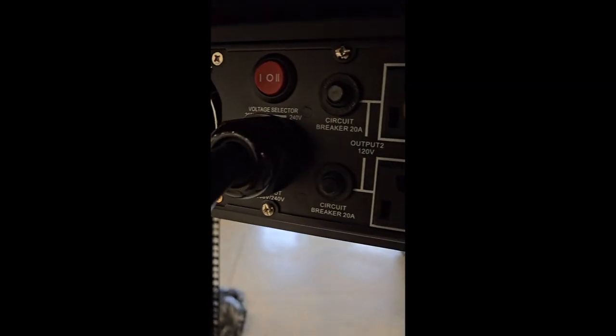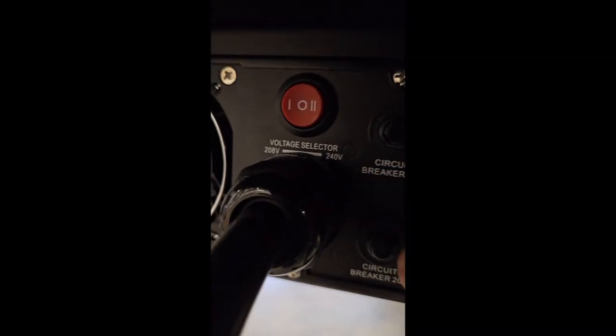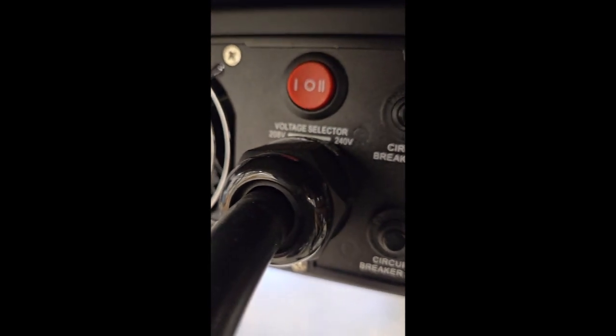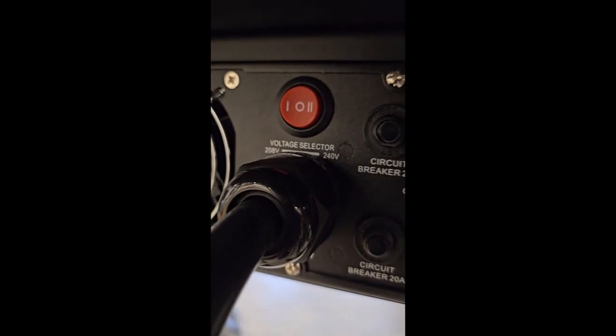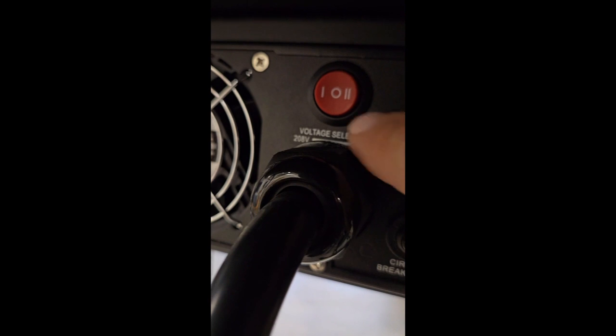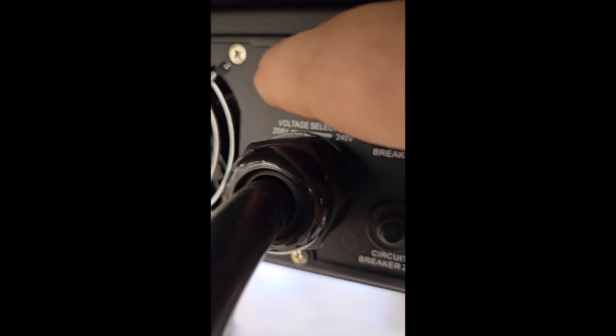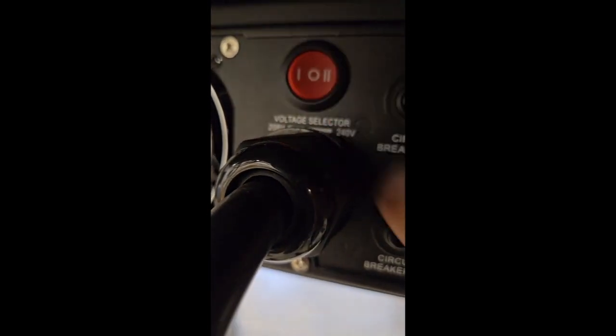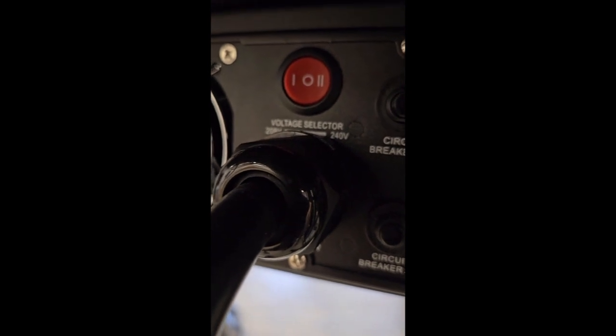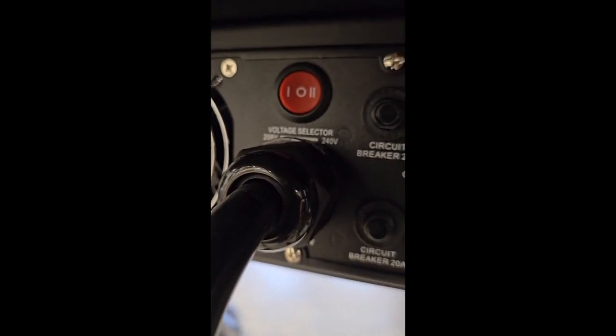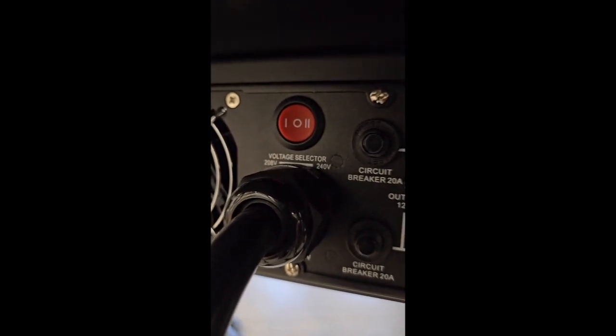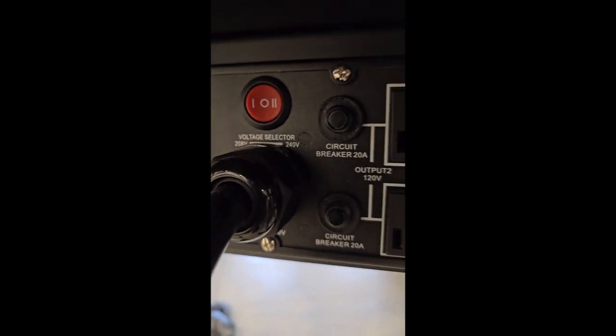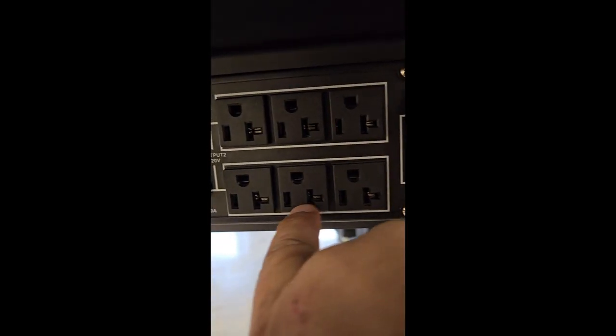One thing to be sure of is on the transformer module, there's a switch. The UPS will operate at either 208 or 240 volts. It's important that you select either 208 or 240 volt based on the UPS input to ensure that we have 120 volts line to neutral on our 120 volt receptacles.